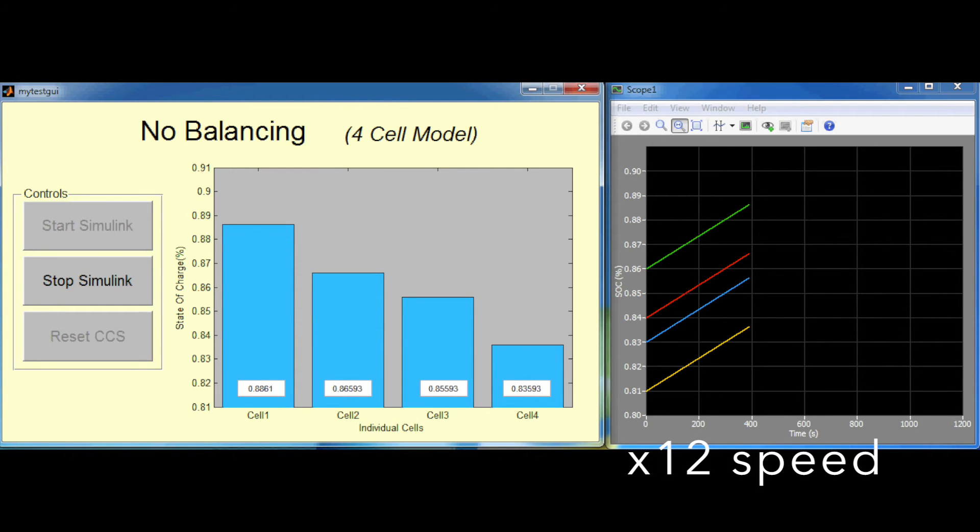Therefore, to avoid over-voltaging the cells, charging is limited by the cell which has the highest SOC, which in this case is cell 1. The pack then can never be fully charged to its rated capacity since most of the cells will not be able to reach 100% SOC.